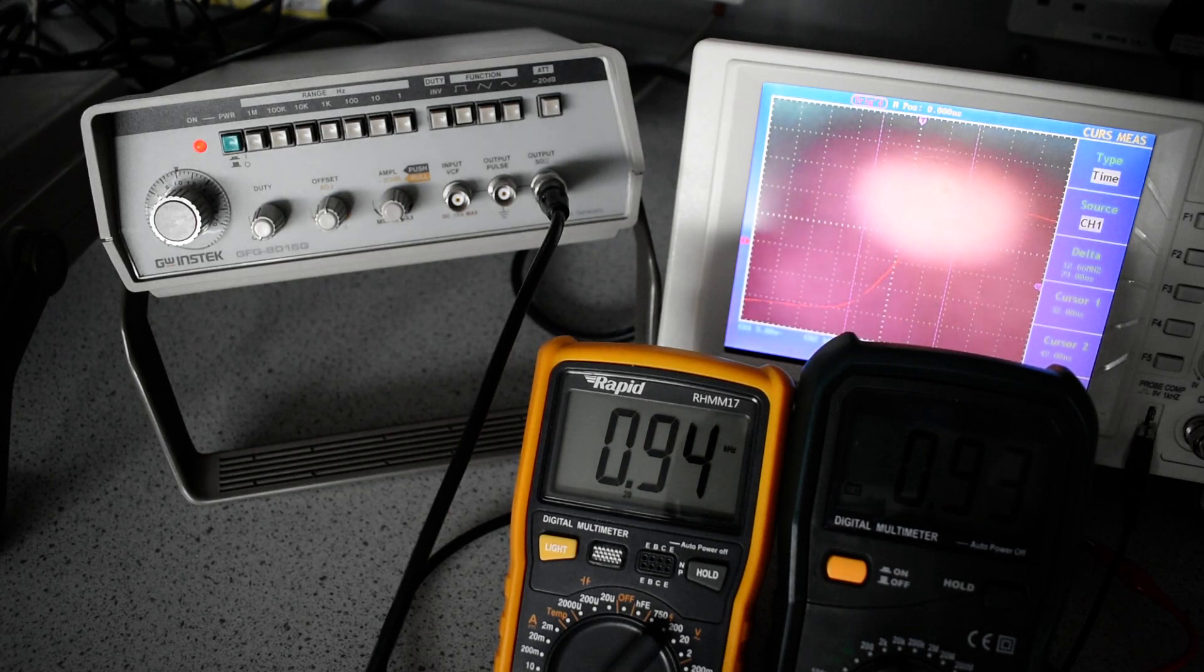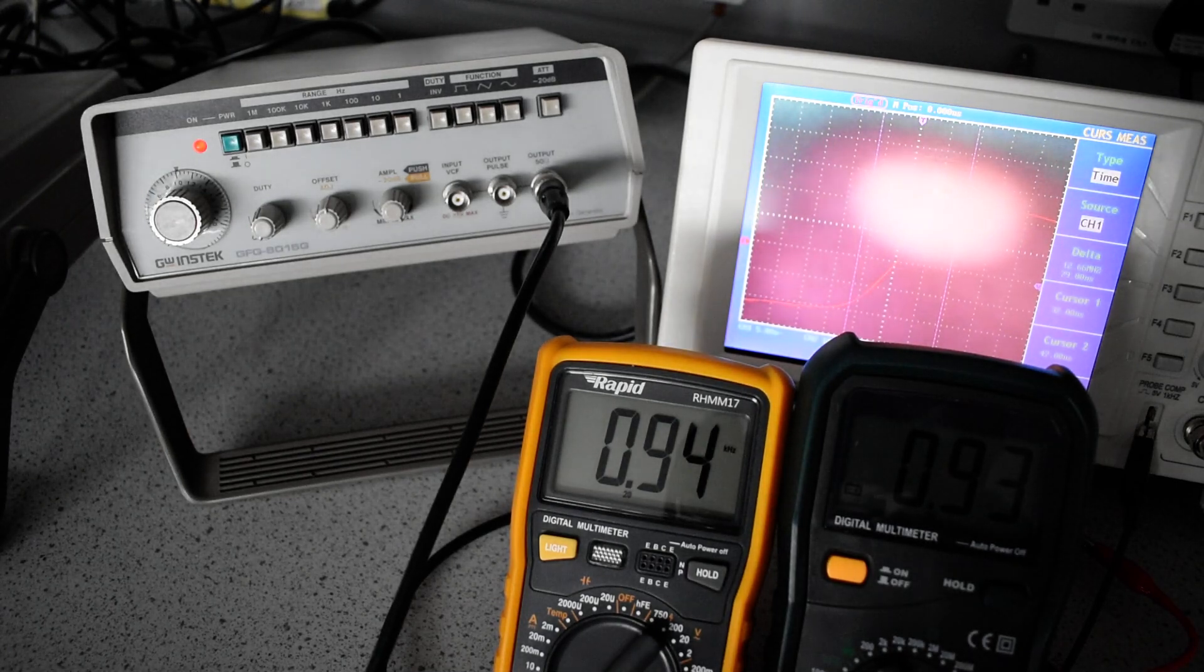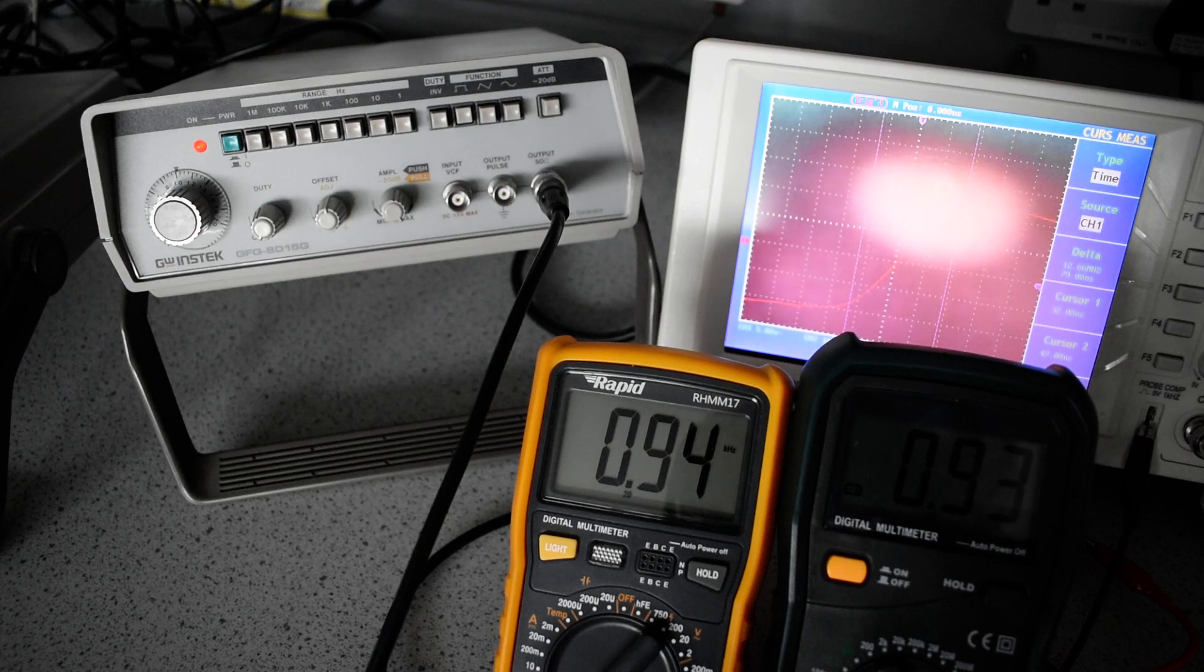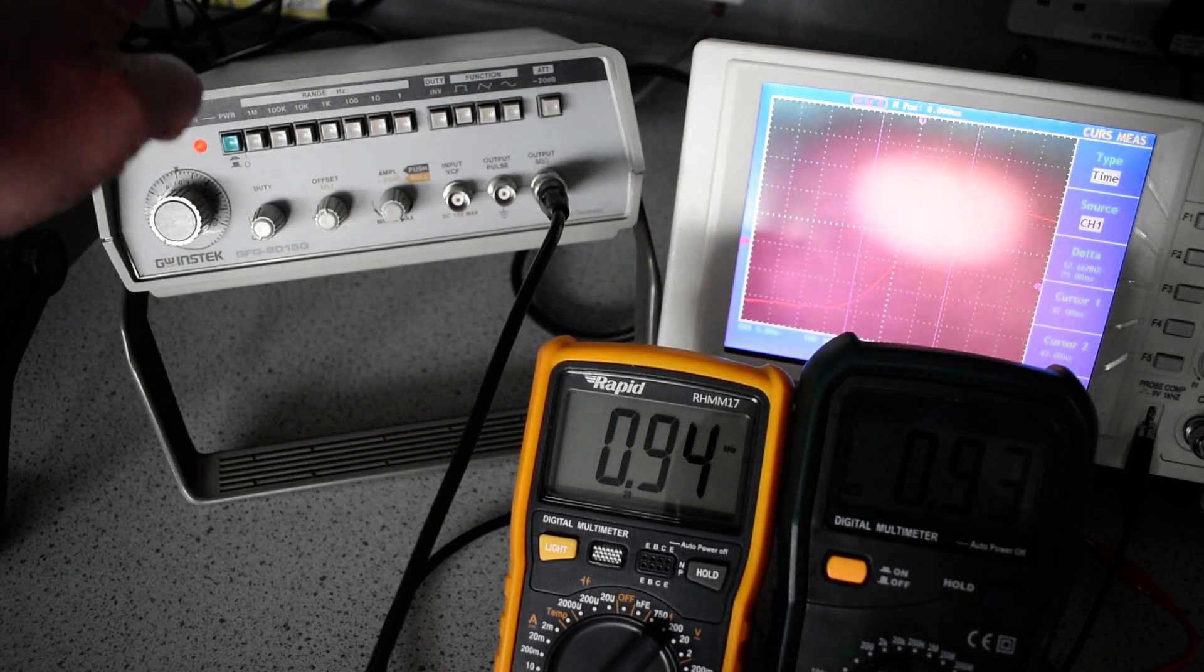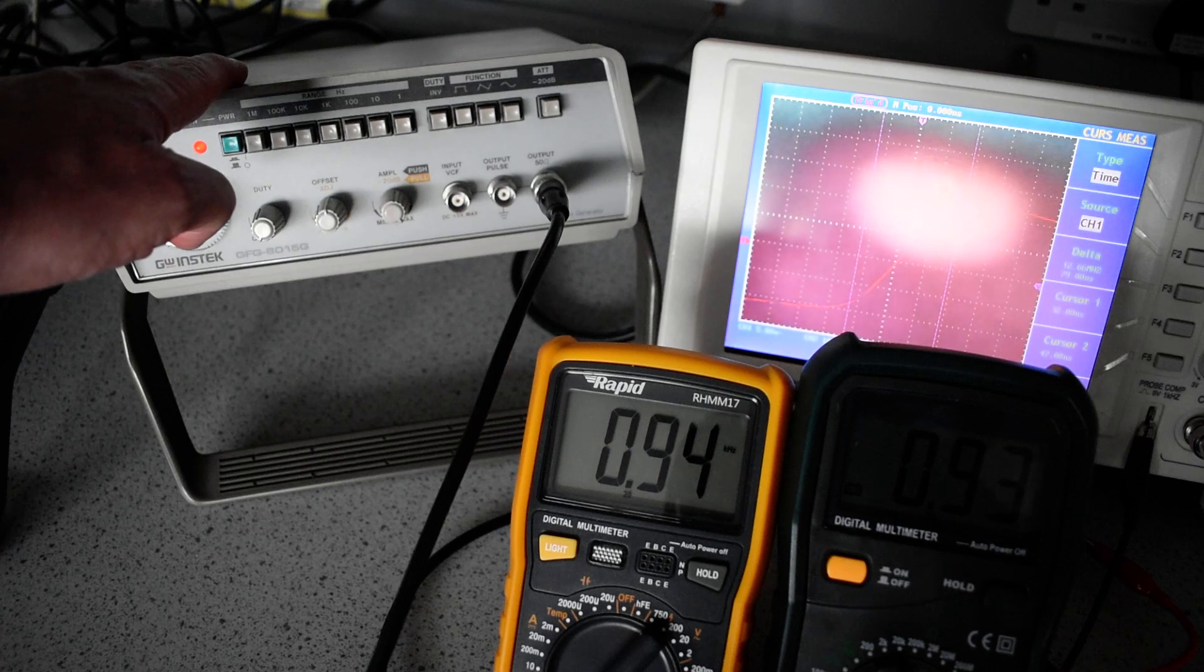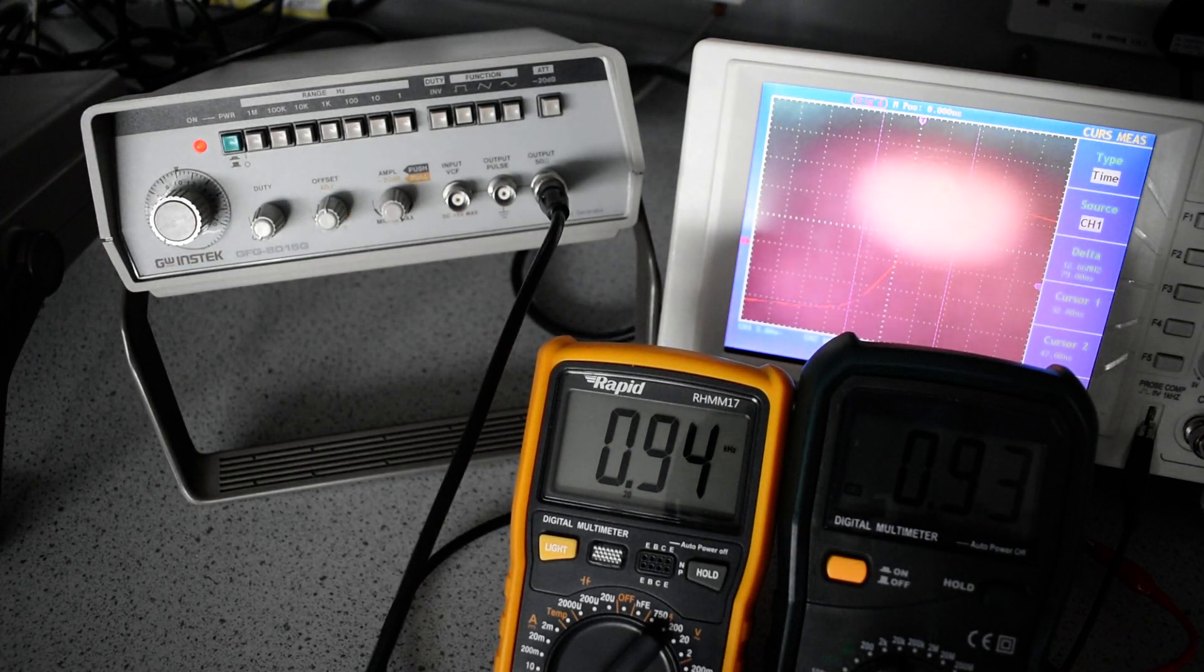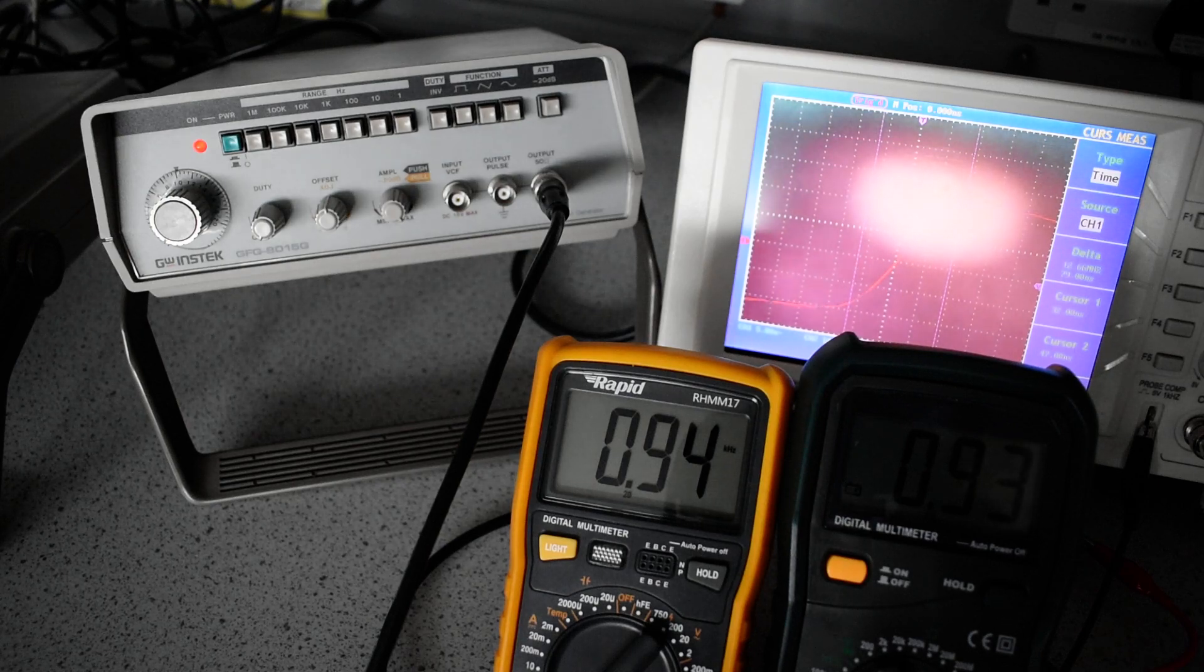So, the summary of this calibration demonstration is we've measured the amplitude and output frequency of two different signal generator boxes. This one is out of specification, not fit for purpose. The first one we did was still within specification. Thank you.